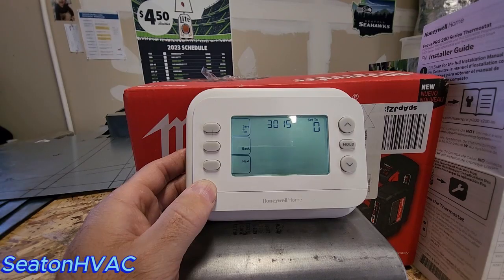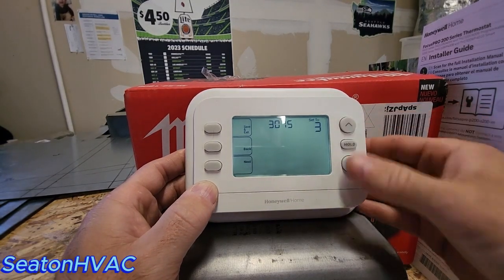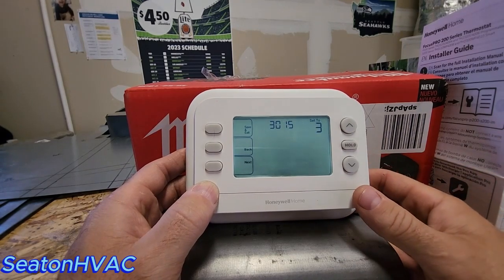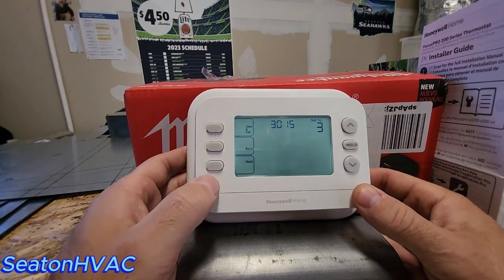All right, 3015 is your auto changeover differential. 3 is what it comes out of the factory as. So that's what you want to put it at. You want to make sure it stays at 3. You don't want it cycling back and forth between heat and cool. So you want to leave that at 3.